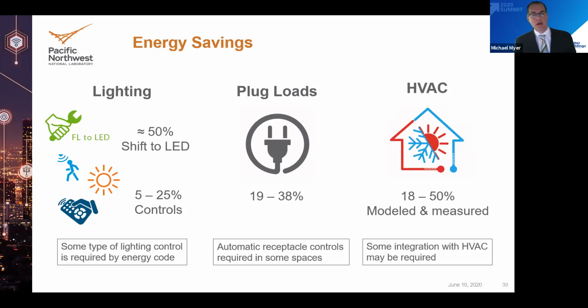We also analyzed a number of reports and projects related to HVAC integration, using occupancy-based control to set back temperature, fan, and other functions. That saves somewhere between 18 and possibly even 50%, combining modeled and measured results. I'm always a little cautious on modeled results—they tend to run higher than practice—so I'd say HVAC controls are probably in the mid 20 to 30% savings range. But that's substantial given the size of the overall HVAC load, so it's still really worth considering.